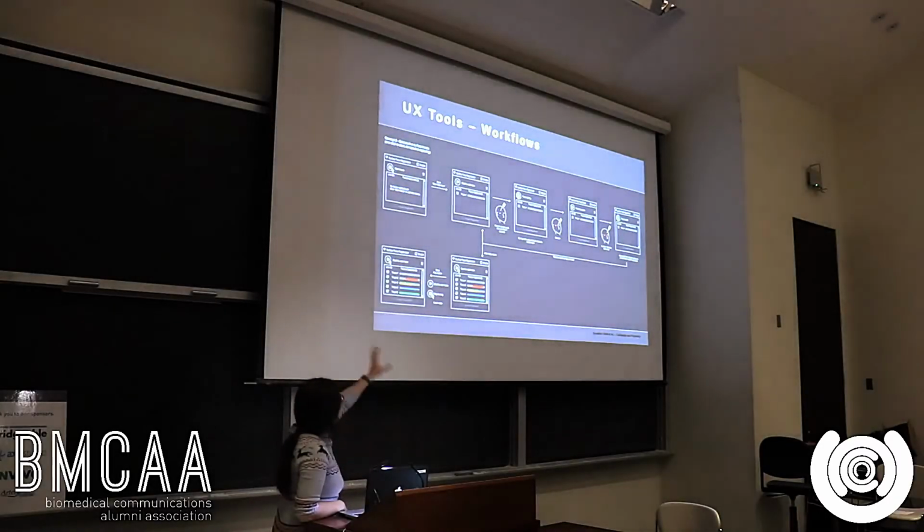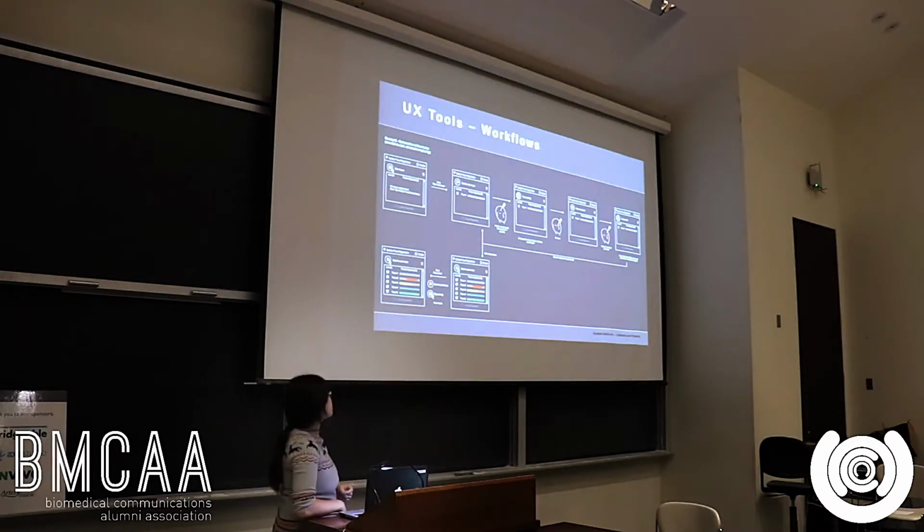This is our navigation system. What a lot of users have to do is very complex steps to register their patient, register their tools, and to know where they are in the navigation space. So we also do workflows for them, step by step, what you will see in the UI, what happens, what you do with your tool. Right now, they're tracing a little mask on the patient to register their contours in 3D space.